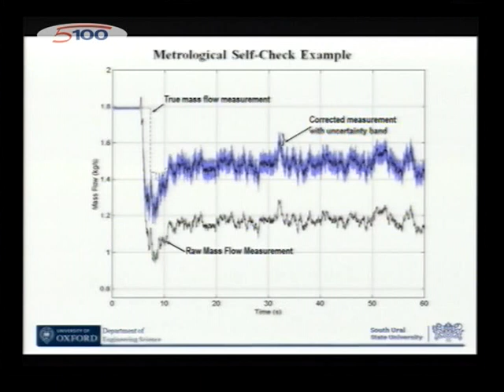So in this example here, this is data generated from a Coriolis meter, a mass flow meter. The measurement is fine up to this point, and at this point a fault occurs, and the raw measurement is faulty, so there's an error in it. But instead of generating this false data and just supplying it with an error code, the device corrects the measurement internally to provide a corrected measurement, and also provides an uncertainty band showing how good the measurement data is.